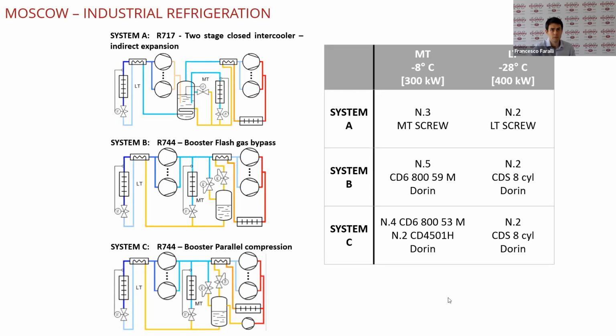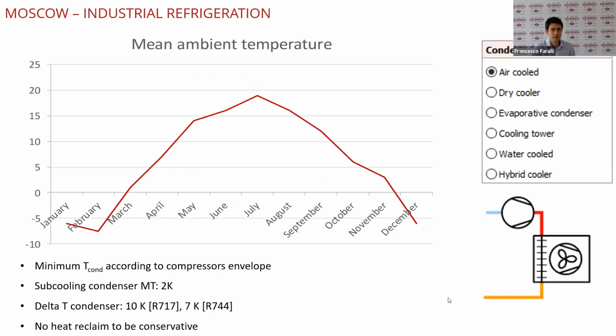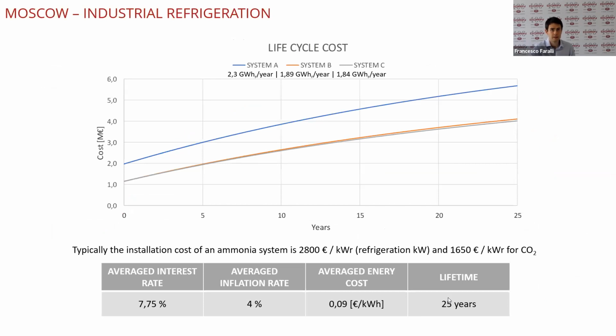This comparison was performed in Moscow during the year. This is the mean ambient temperature and the assumptions we have made: it's an air-cooled condenser with 2 Kelvin subcooling and 10K delta T at the condenser for ammonia and 7 for CO2. And here are the results with the life cycle cost. System A is the blue line with ammonia, and systems B and C are more or less the same and are the CO2 systems. The assumptions we have made are 2,800 euro per kilowatt of refrigeration, assuming this is the cost of an ammonia installation of this size, and 1,650 euro per kilowatt of refrigeration for CO2.